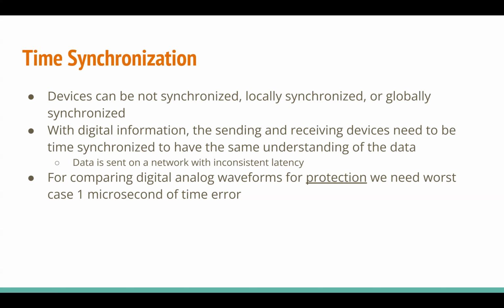When we're sending data over a network, we don't always send data with the same amount of latency. So we can't just rely on sending data for the other device to understand when it was sent. If we send a sample of a waveform at time equals 0, the first time it might get to the other relay at 5 milliseconds in the future, the next time 7 milliseconds after, or 3 milliseconds after. So we can't just calculate against the latency and say this is always going to be the difference. That doesn't work.